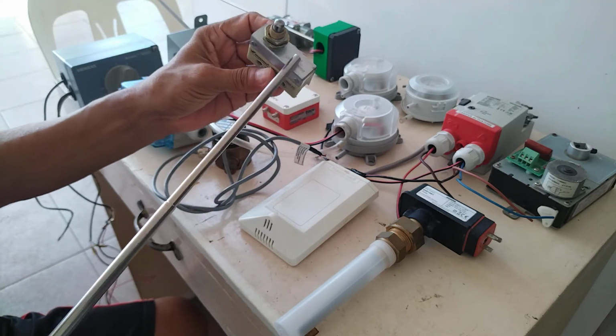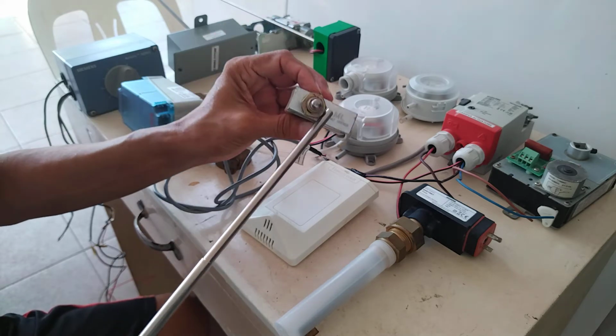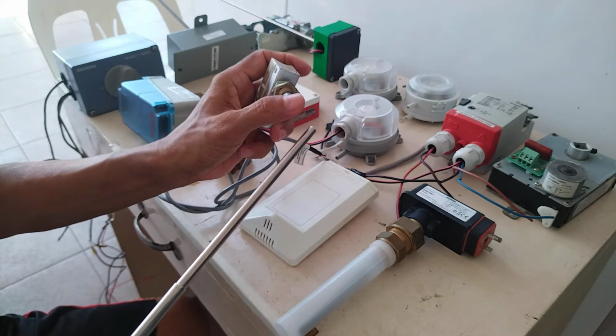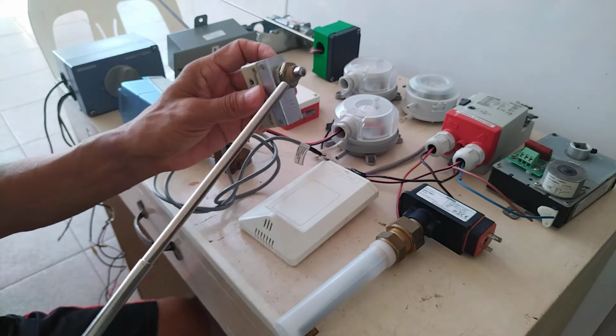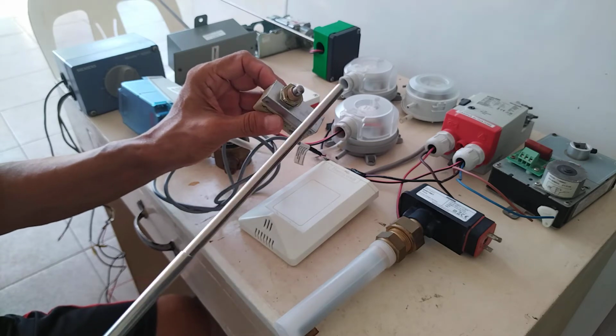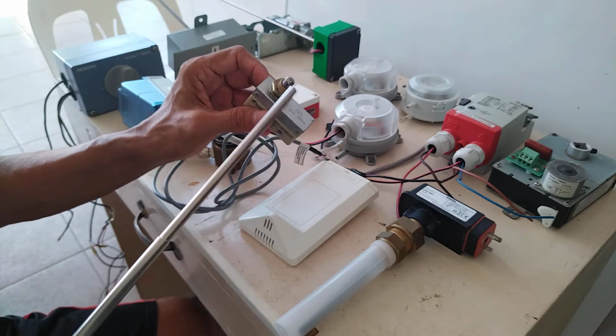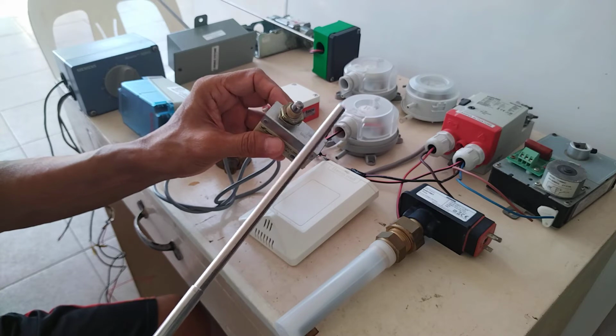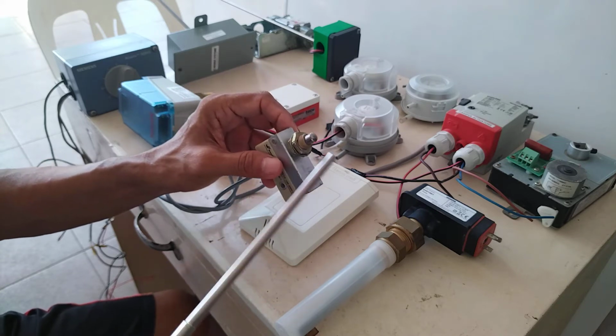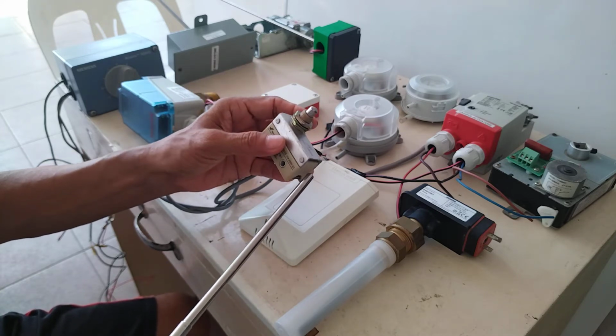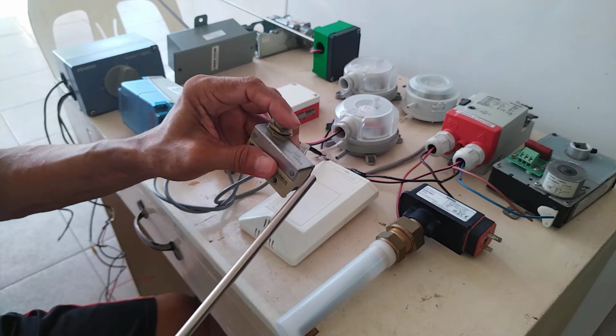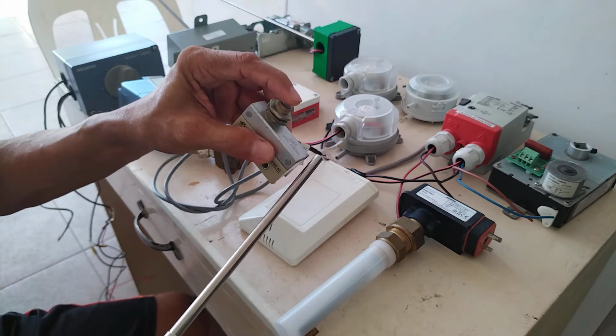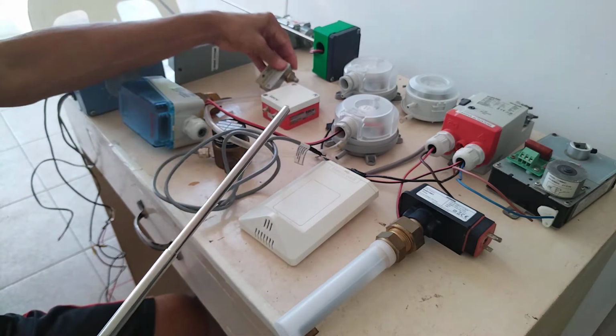We are usually using this for the air handling unit door, okay? Because for the air handling unit door, we want to know whether it is always shut, closed, or open, because we cannot leave the air handling unit door open. It should be off. So this one will sense if the door is open or closed. This one is called a limit switch, okay?